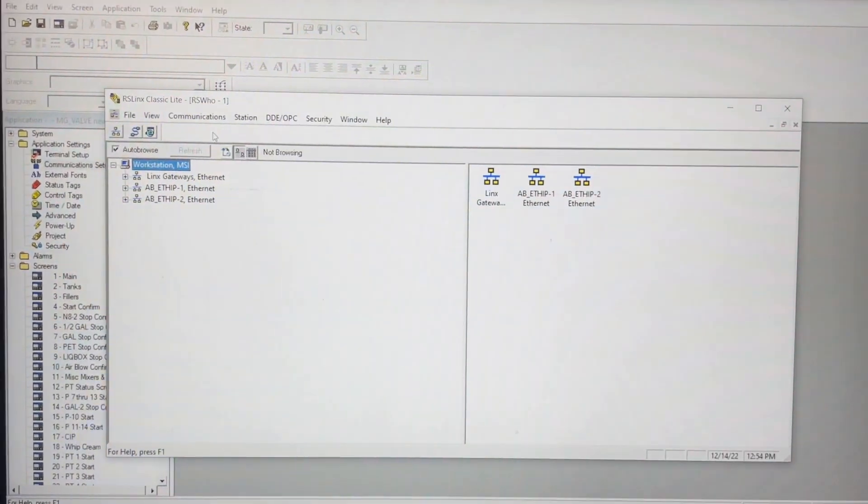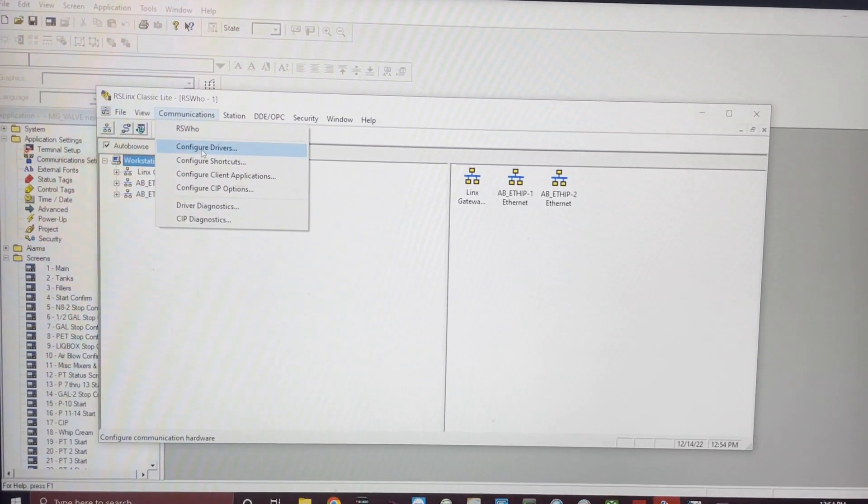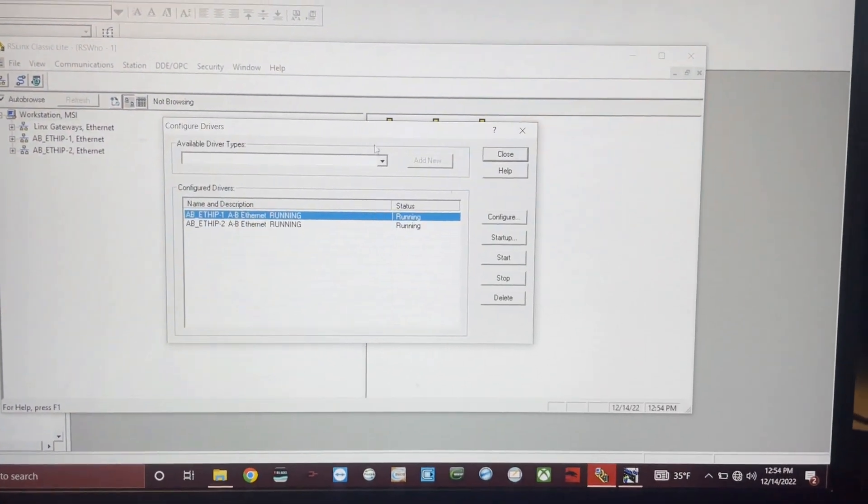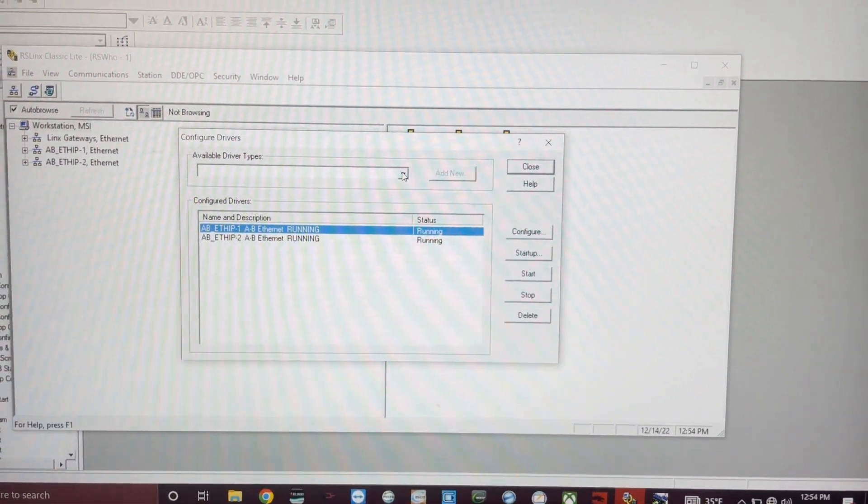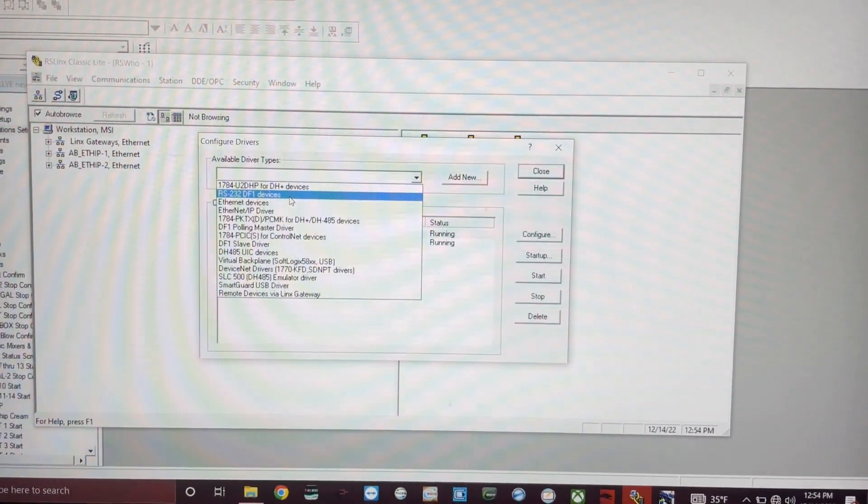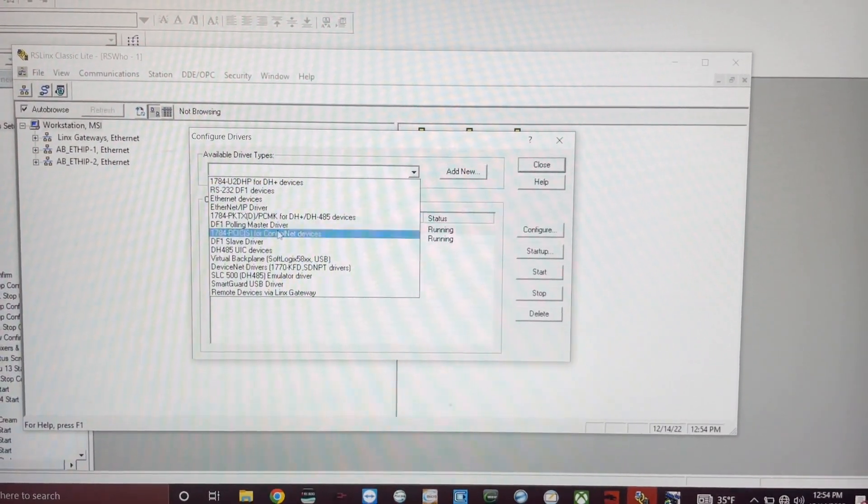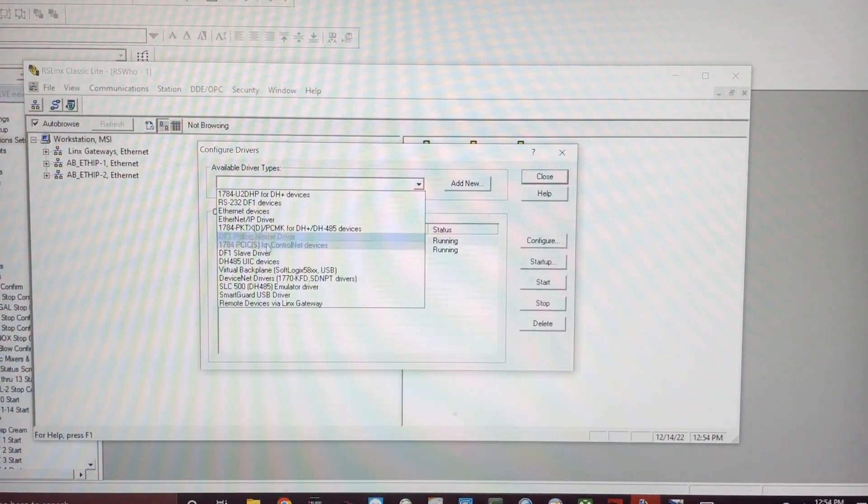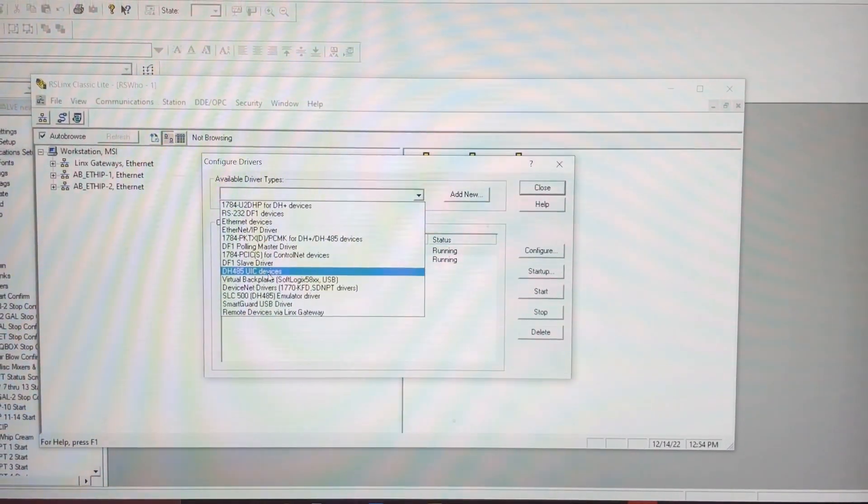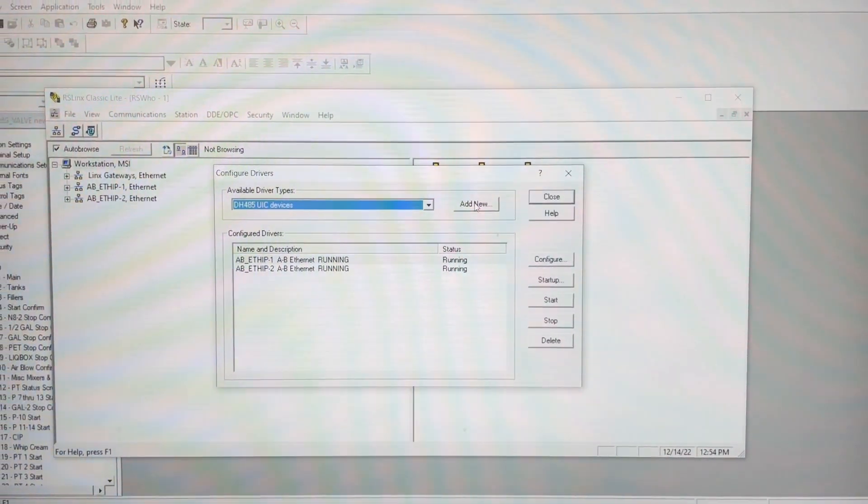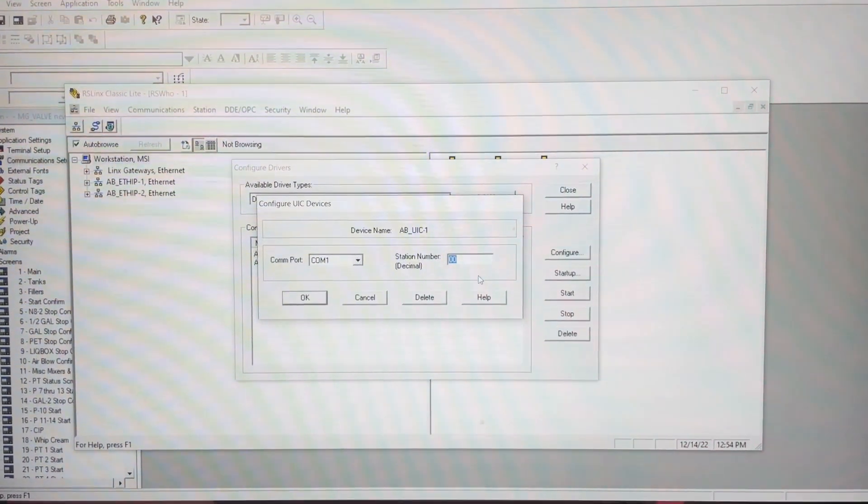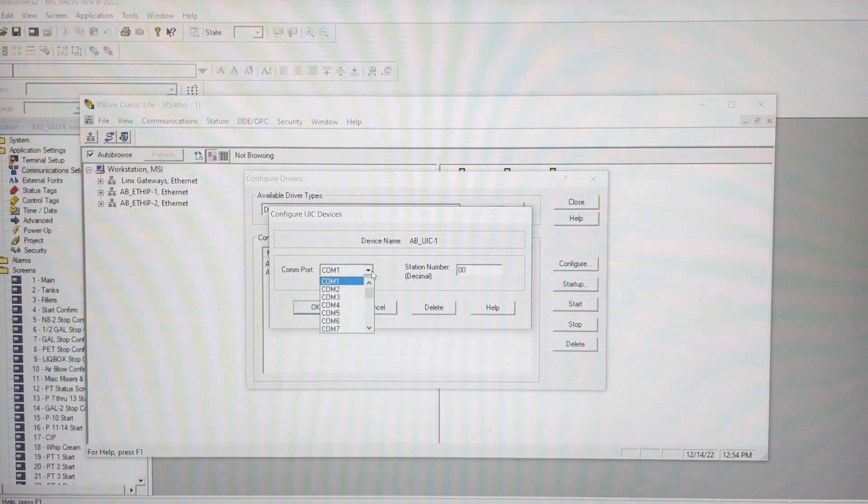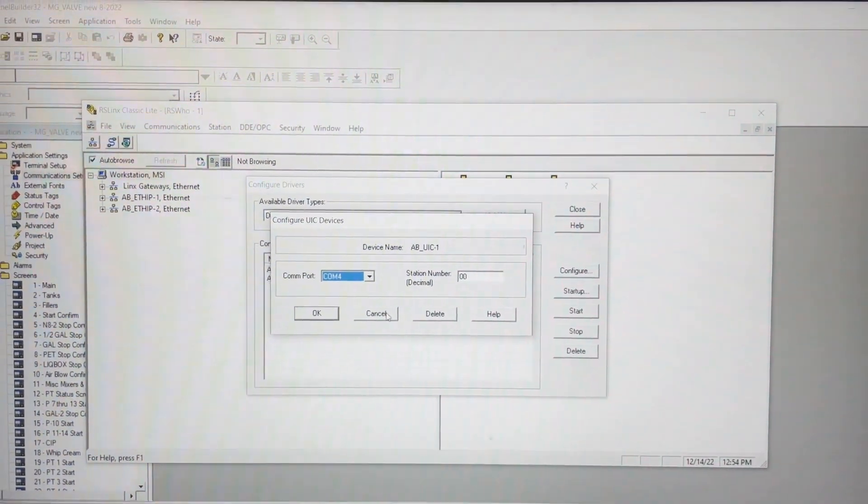Now that we've verified it's COM 4, we're going to go back to RS Links and go to Communications, Configure Drivers. In our available driver type, we'll click the drop-down arrow and find our DH-485 UIC devices - right there, that's the one. We'll hit Add New. Doesn't matter what you name it - hit OK, and then select whatever COM port it was, which is 4 in our case, and hit OK.